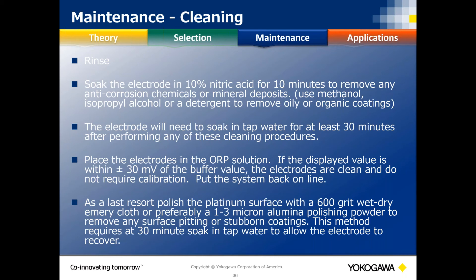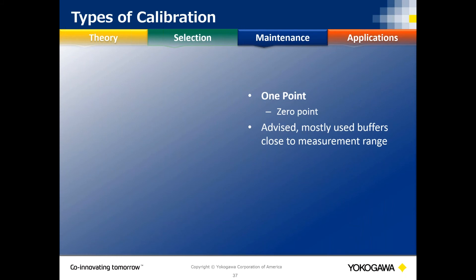If the ORP reading is within plus or minus 30 millivolts of the expected value, you can put it back without recalibrating unless your SOP requires it. The platinum or gold pin can sometimes be refurbished with an emery board to scrape off adhered deposits, but make sure you allow enough time for the pin to re-acclimate afterwards.